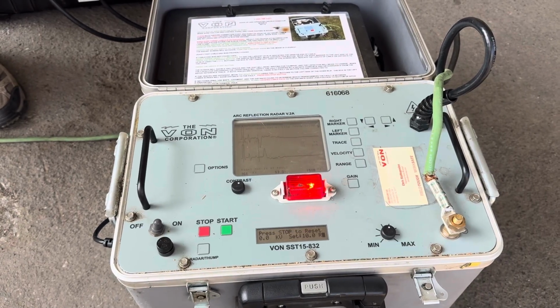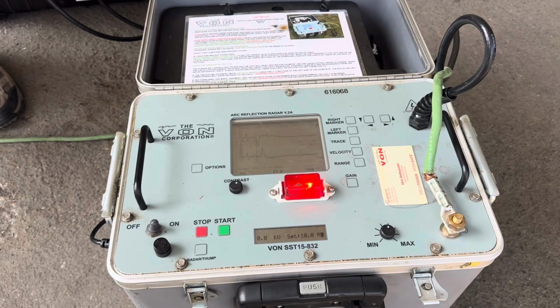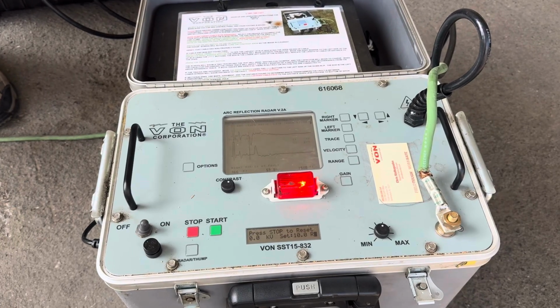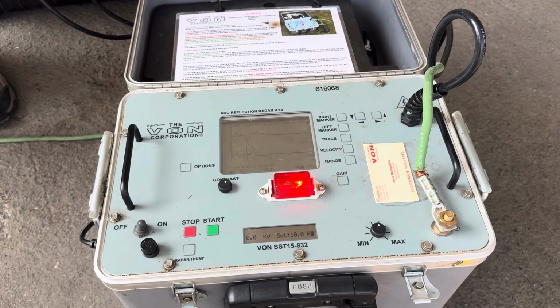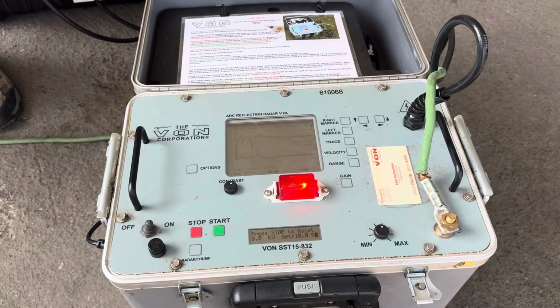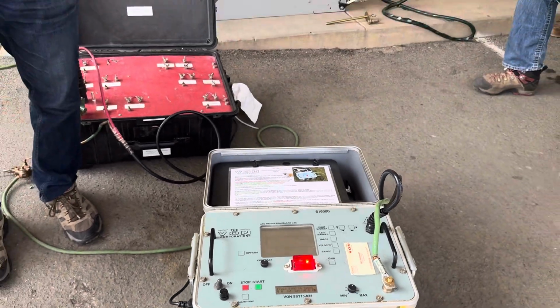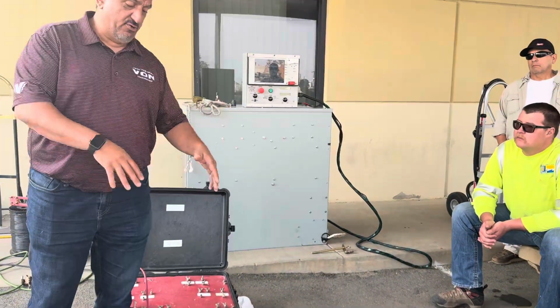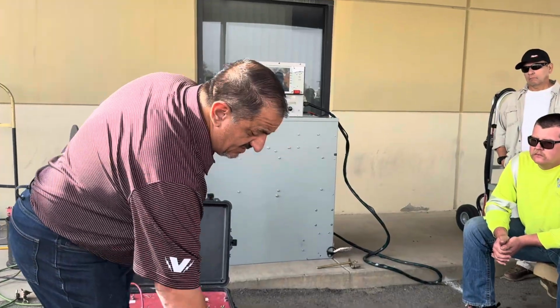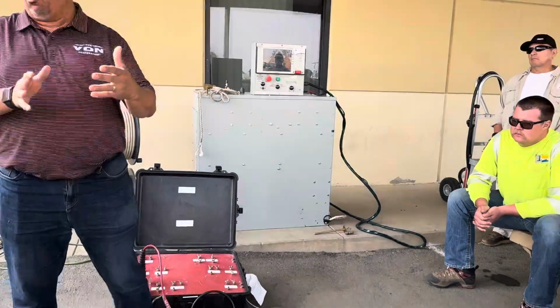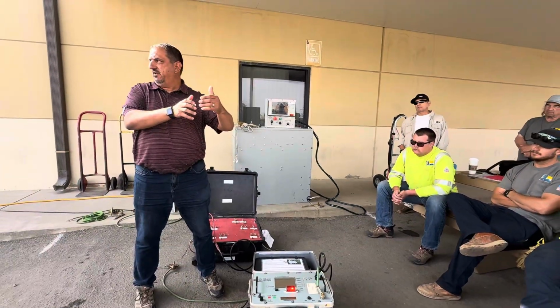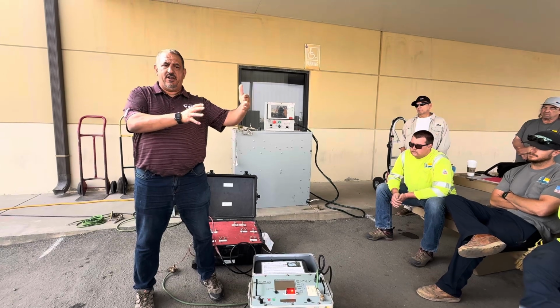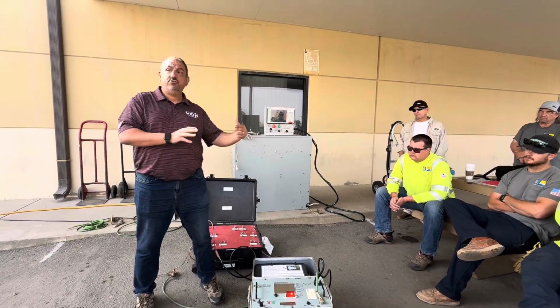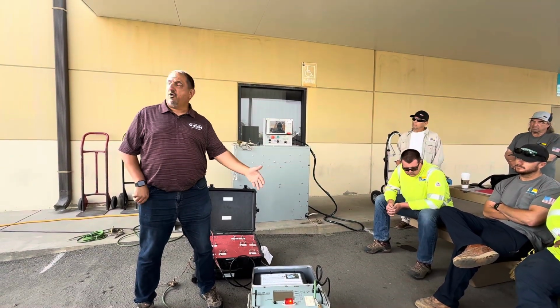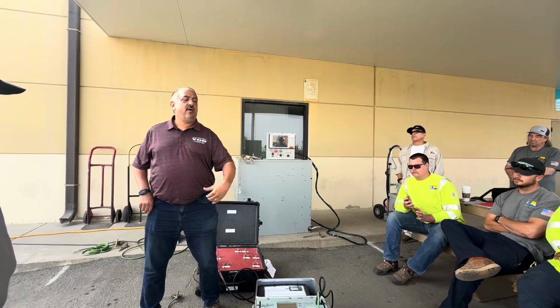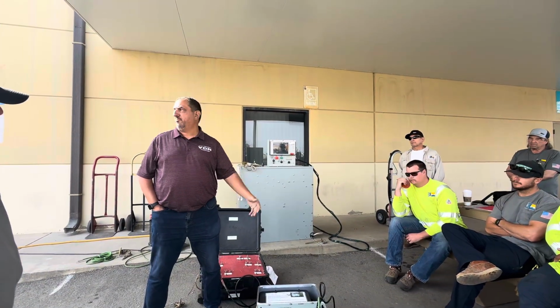Yep, exactly. So in a situation like this, what would you do? Now I've got my hookup, a couple of transformers, my normal open. Now we determine it's between the second and the open. So at this point I would push the stop button. Let's isolate that section. Go pull the elbow to the second transformer, and then isolate it to the normal open, and then do this whole process again. Radar the cable, find out where the fault is at. Then once you've done that, you can thump the cable.